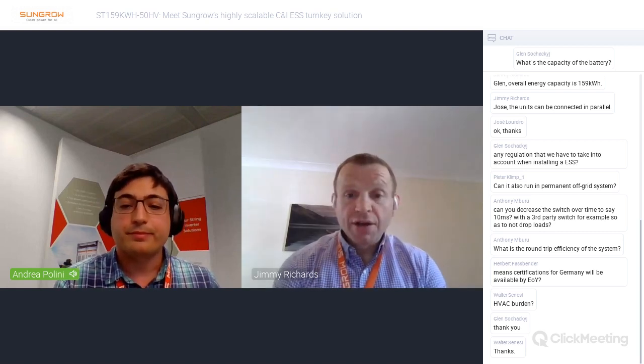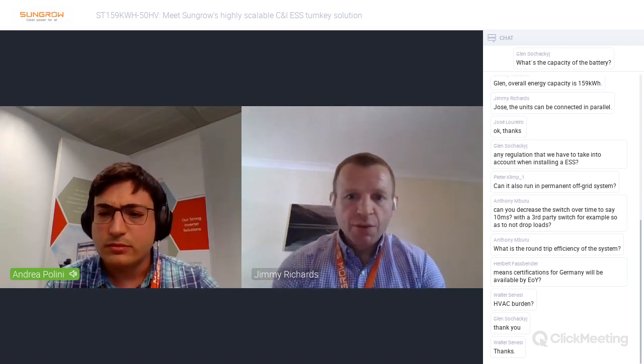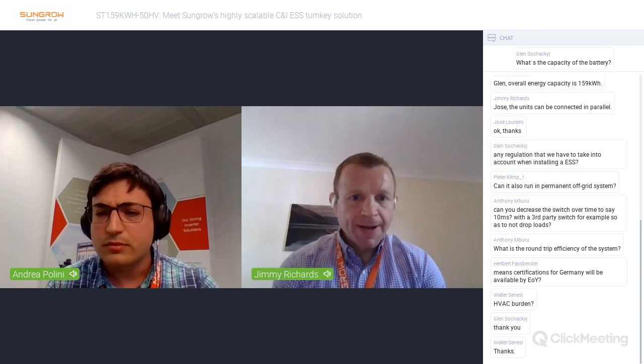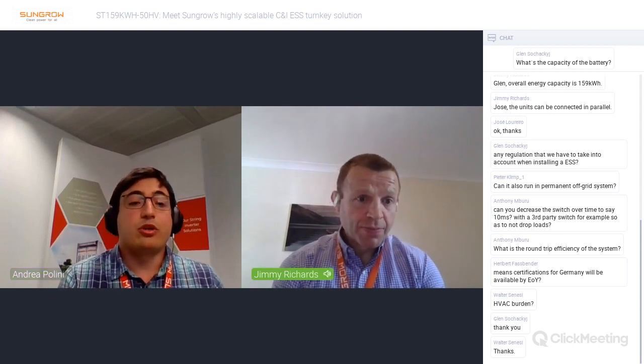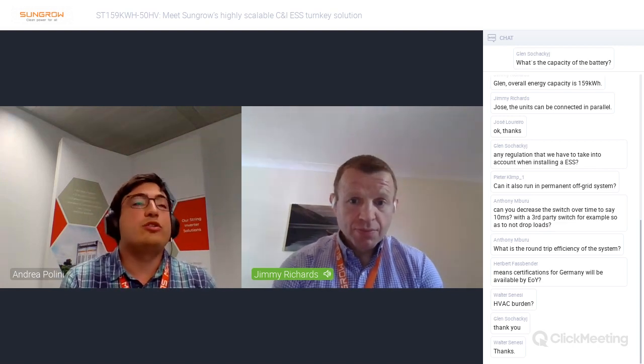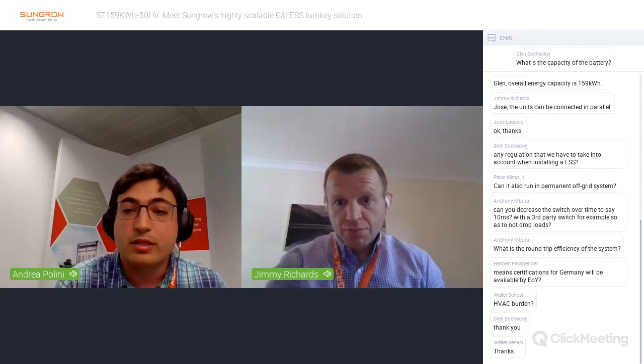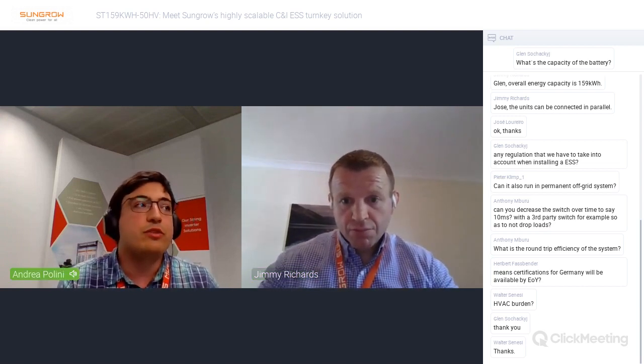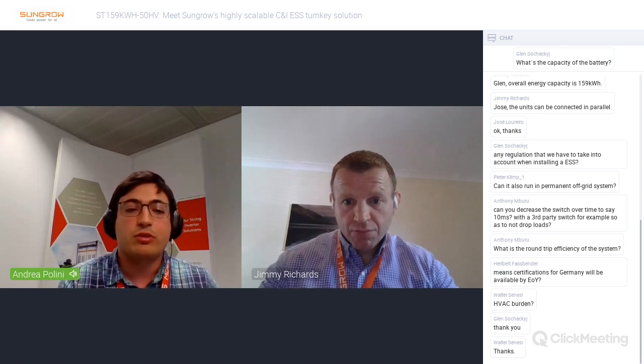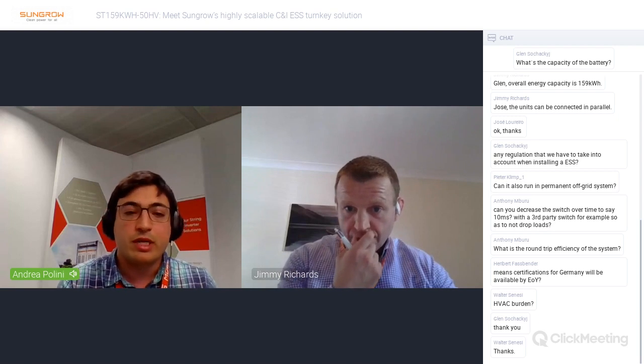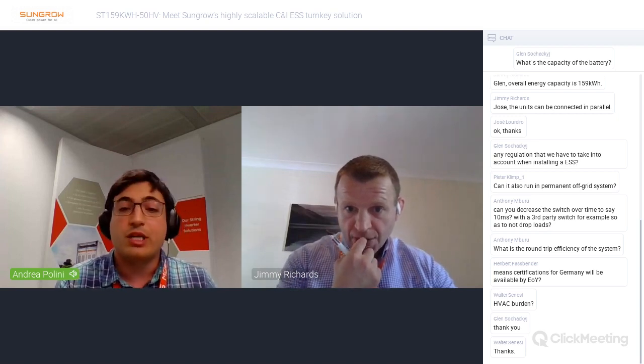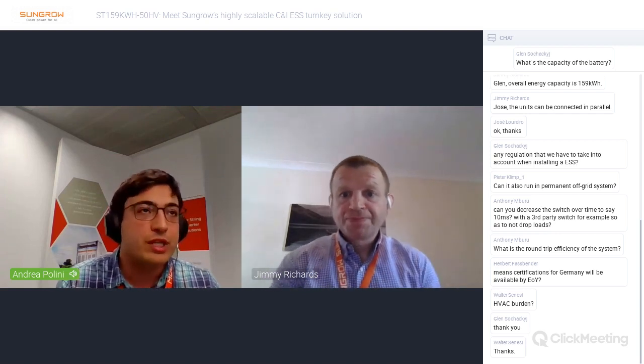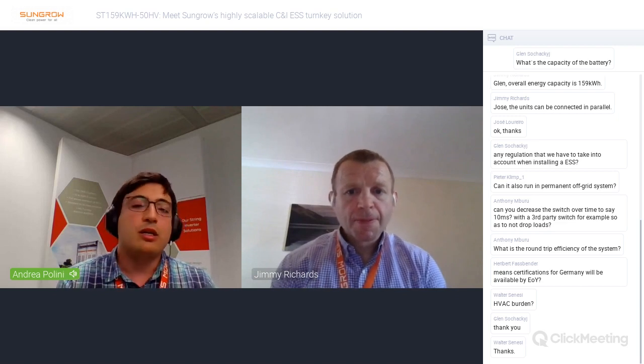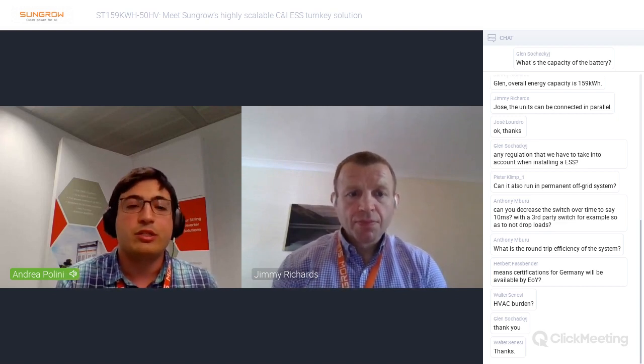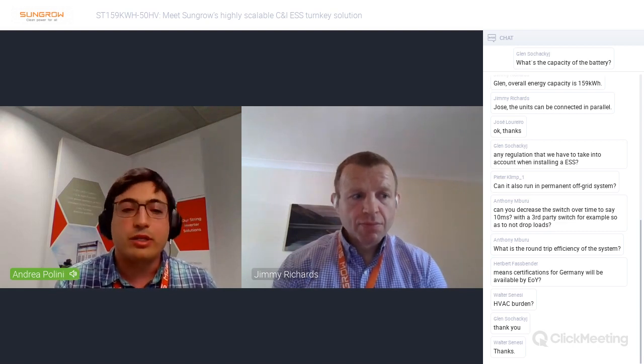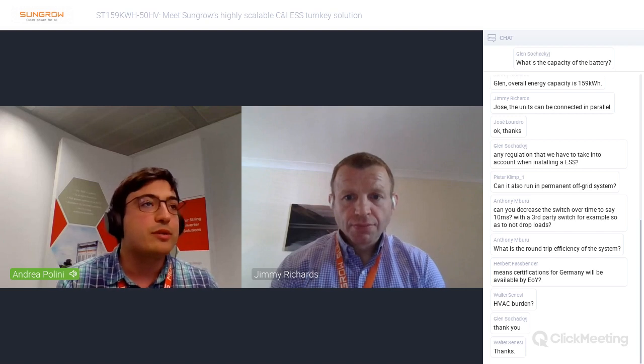Okay, good stuff. Glenn comes in with a follow-up question: are there any regulations we have to take into account when installing an ESS solution? Yes, sure. The general regulations are grid code compliance, which is required for any generation or storage product to connect to the grid with automatic disconnection devices. In Germany, for example, we follow the VDE 4105 and 4110 standards. In the UK, you have the G99, G98, and G100 regulations. These are the regulations we should comply with in case of grid connection points.